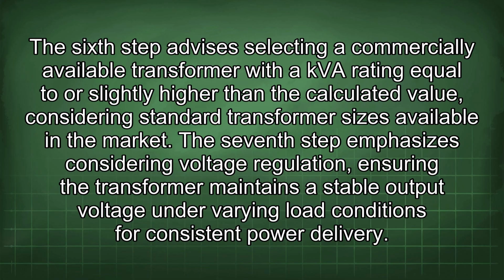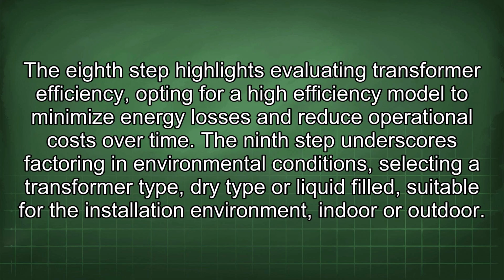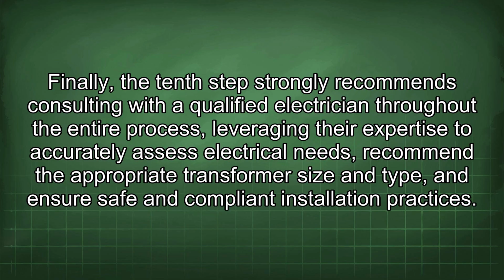The seventh step emphasizes considering voltage regulation, ensuring the transformer maintains a stable output voltage under varying load conditions for consistent power delivery. The eighth step highlights evaluating transformer efficiency, opting for a high-efficiency model to minimize energy losses and reduce operational costs over time. The ninth step underscores factoring in environmental conditions, selecting a transformer type, dry type or liquid-filled, suitable for the installation environment, indoor or outdoor. Finally, the 10th step strongly recommends consulting with a qualified electrician throughout the entire process, leveraging their expertise to accurately assess electrical needs, recommend the appropriate transformer size and type, and ensure safe and compliant installation practices.